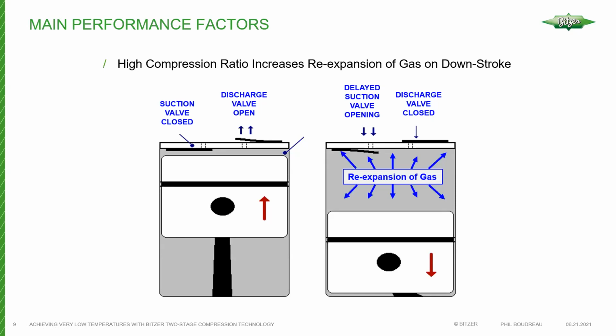When I mentioned before that the higher compression ratios get, the more challenging it becomes, it's because we run into situations with the re-expansion of gases. Just imagine compressing that refrigerant and then the piston reaches the top, but it never goes all the way to the top. We need to leave a bit of space because we never want the top of the piston to come into contact with the valve plate and the suction reed valves and what have you. So there's always a bit of a gap. With that high pressure trapped up there, when the piston starts traveling downwards, that trapped refrigerant will re-expand. And the higher the compression ratio between the discharge and the suction, the more of that stroke is used up re-expanding that refrigerant. So you can essentially get to a point where those pistons are going up and down and just compressing refrigerant, and your overall throughput, which we call mass flow rate, is less.